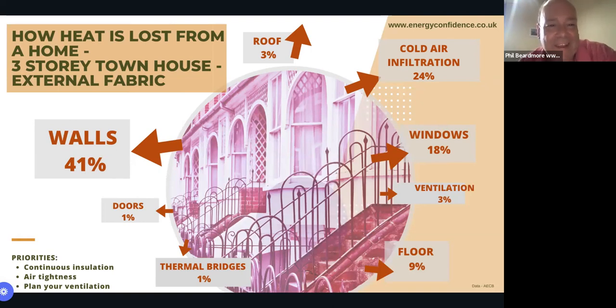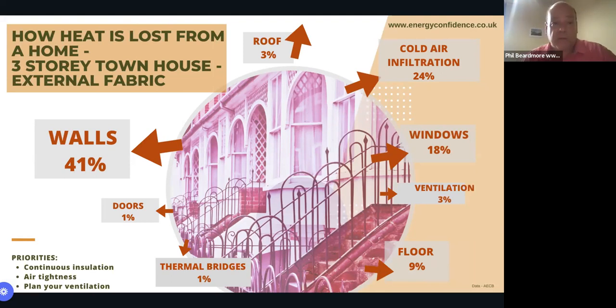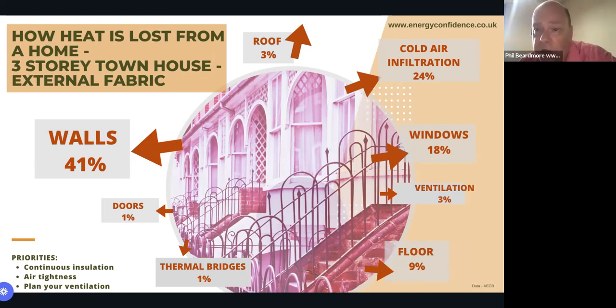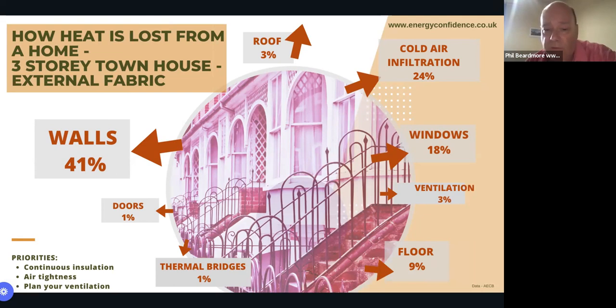Next is a three-storey mid-terrace townhouse — the houses in Link Road are mostly three-storey mid-terraces. Again, most of the heat loss is through the walls, some through the floor, and a lot through cold air infiltration — general leakiness especially where there are pipes, cables, and services going in and out of the building.